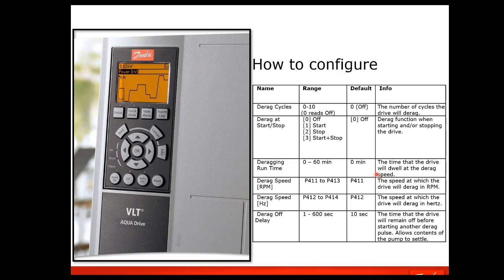The run time is the dwell time for running at speed. The deragging speed is selectable, and there are two parameters here based on the main parameter drive, whether the speed settings are based on RPM or Hertz. And then the derag off delay, between running forward and stopping, and then running backward and stopping. This is the setting of the time between those, allowing maybe solids to settle or anything like that to help it get clear.